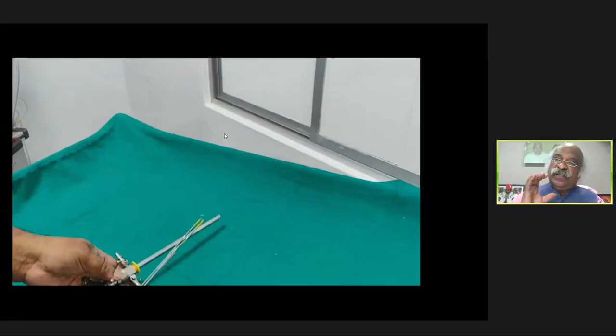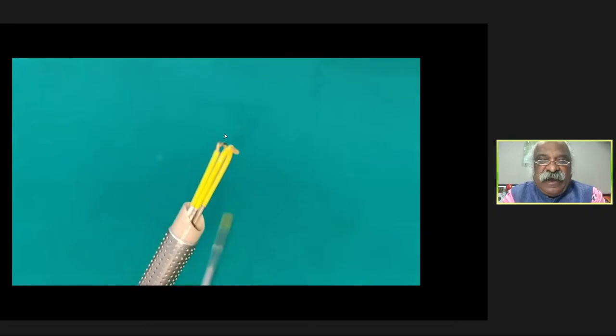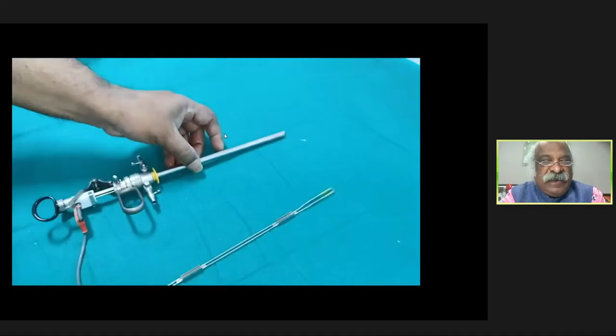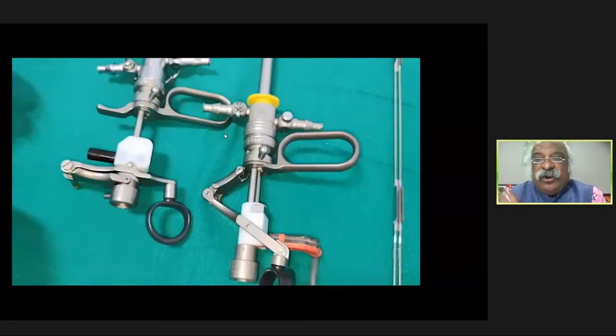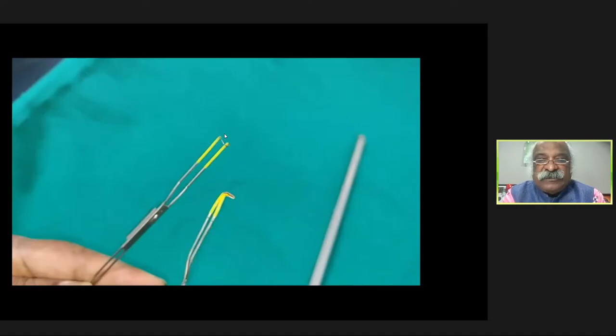You can see the two inserts, the difference between the unipolar and bipolar setup, and the electrode. The resectoscope is also different in both cases. Here you can see the tip of the loop connected with the bipolar resectoscope, which also looks different. This is an assembly with the Collins knife, with the cable attached. In contrast, the unipolar has two prongs, and the same Collins or loop can be inserted. There is no connection between the two.